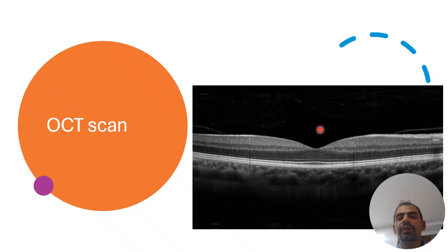This is how the machine shows the scan of the macula. It can clearly delineate the different layers of the retina as if we are looking under the microscope. It's again capable of giving the details of the choroid and the choroidal vessels. Those areas with whitish reflex, the reflected light from the eye is in phase with the light reflected from the reference mirror, and those dark parts are out of phase, so the machine is capable of detecting the strength of the signal.